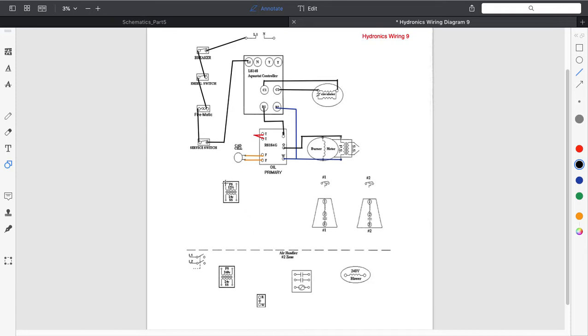I also have to give power to my primary side of my transformer, because we have zone valves, so I have to feed my zone valves. Okay, I also have a neutral here. Okay, neutral is neutral. So let's go ahead and connect that neutral in. Neutral is not switched in most 120 volt circuits. Neutral is neutral. Doesn't matter where you connect it into, neutral is neutral. Now just be aware down here we have a different situation. It's 240 volts, so it does matter. Okay. So that's where we're at so far with neutral.